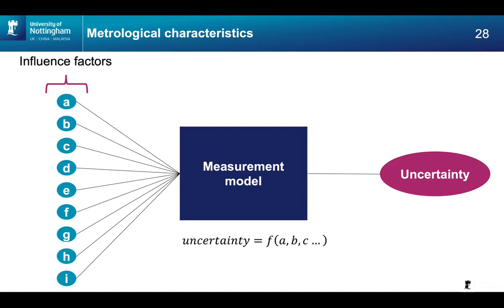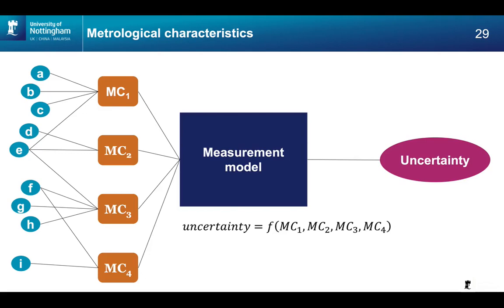The problem is, especially when we've got an optical system measuring the surface, that we've got very complex influence factors. There's many of them. We may not be able to predict them all because we don't have the models of the system, or we've got non-linear models which we can't solve the inverse problem for. And so this list becomes very long and very complex. So what we decided with the metrological characteristics is that we would try to encapsulate all those influence factors in a small number of metrological characteristics. So these are things that we can determine about the instrument, and also maybe the object we're measuring as well in some cases. I'll talk about that.